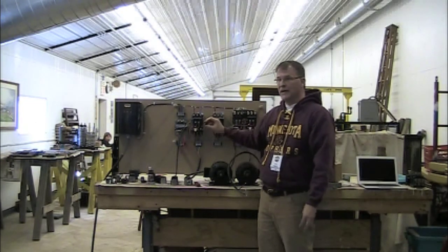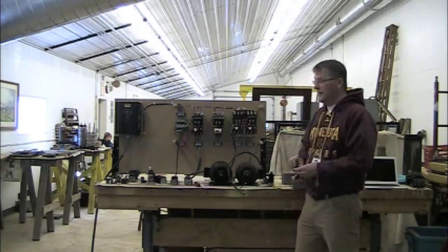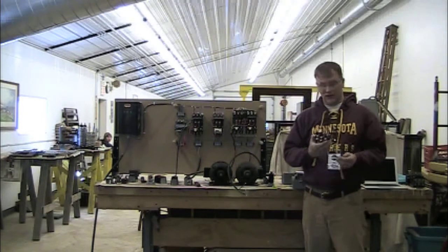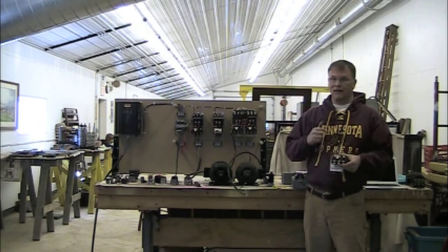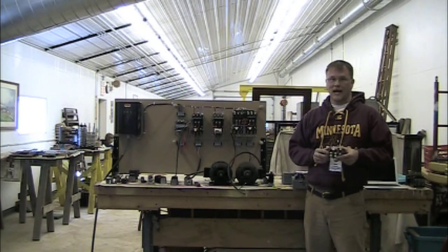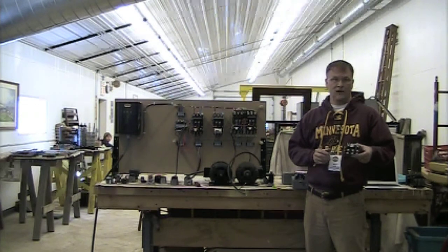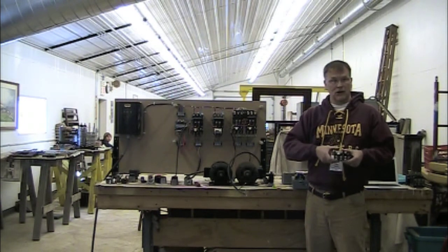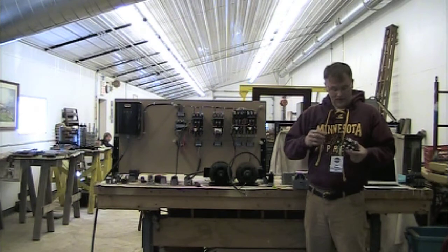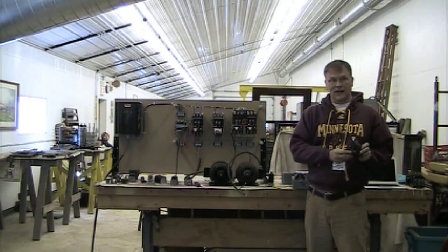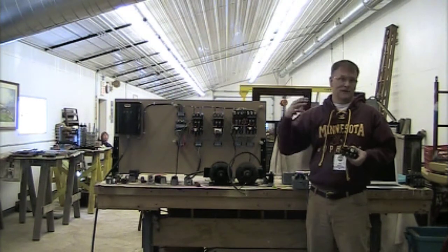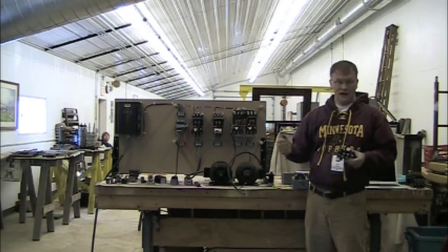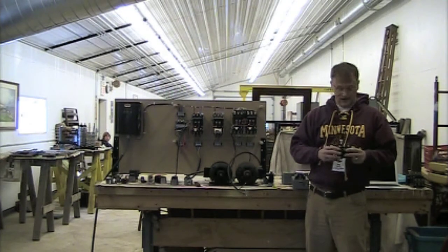And an overload block, when it's got the heaters in it, always has a current path through it. This thing does not break the actual load circuit at all. All it's doing is, it's a set of relay contacts, so when this thing trips, it's designed to trip the control circuit. But there's always continuity across these things.